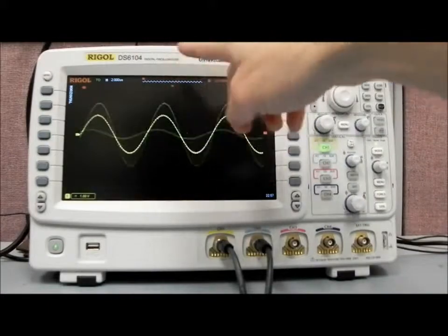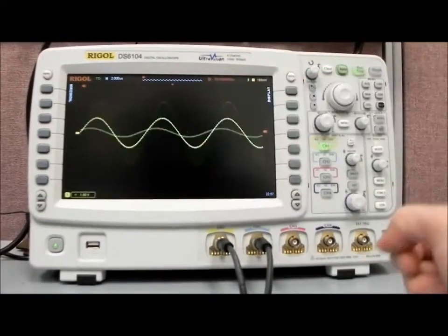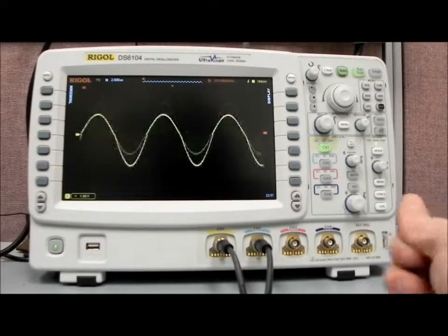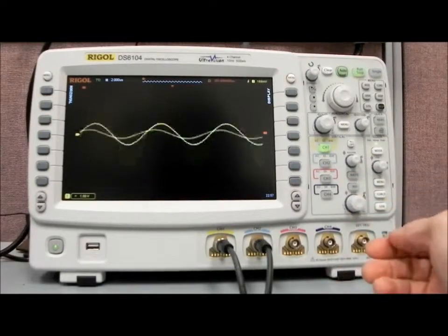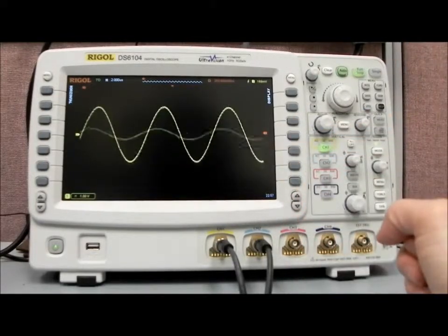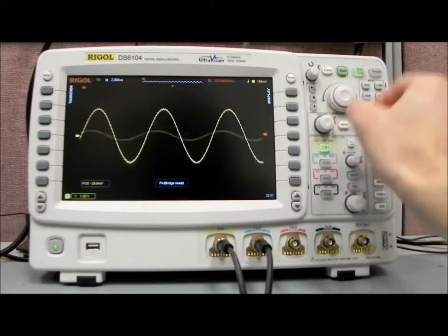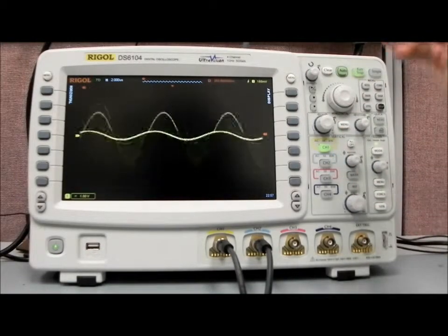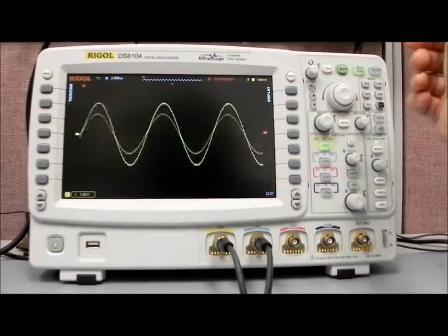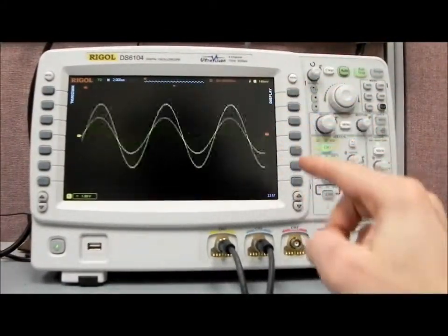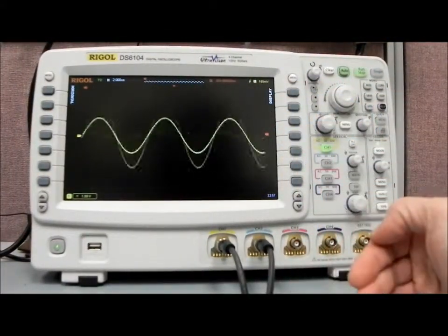So every time the waveform has overwritten in that area, it's made that pixel a yellow color for channel 1, and it's going to stay that way as long as we don't move any of the waveforms. As soon as we move the waveform, it's going to automatically overwrite everything, clear the display, and then start back over again. But what you can do with this is build up almost like a peak hold.